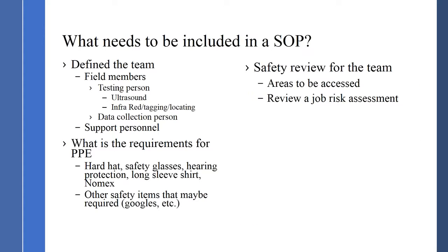Other things included in the SOP: defining the field team members. Who's going to be doing this? Sending one person out is very difficult for any steam trap assessment. So we set up what we call the team — the testing person using ultrasound, infrared, tagging and locating — and another person for data collection. Going out and doing testing without collecting data will not be a successful assessment. There are also support people who input information into the software system we're collecting the data in.